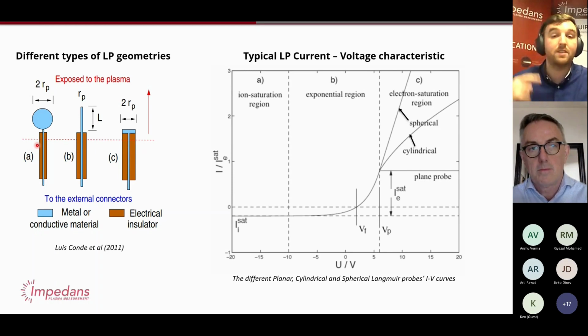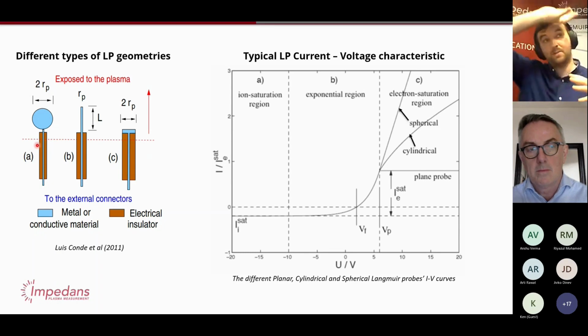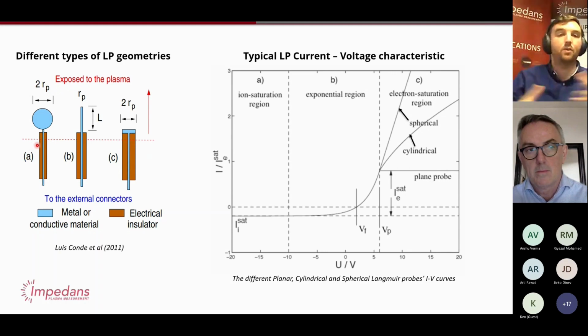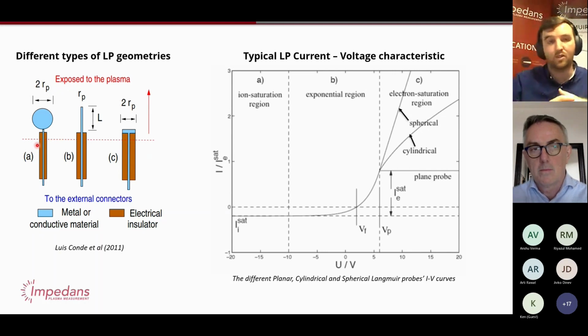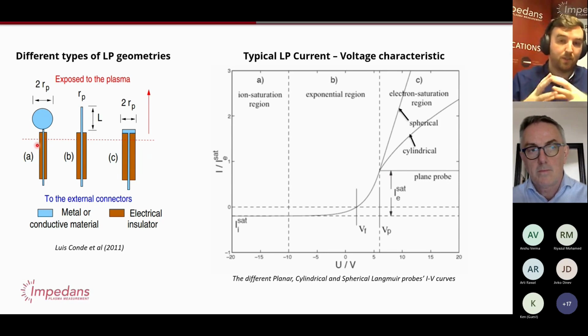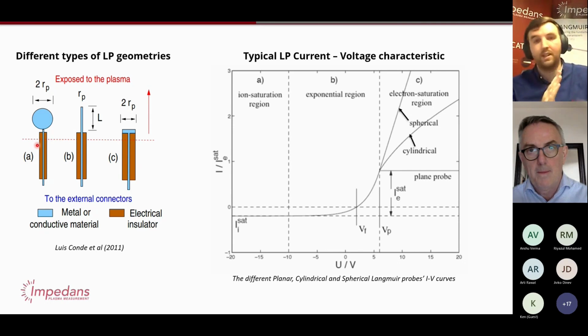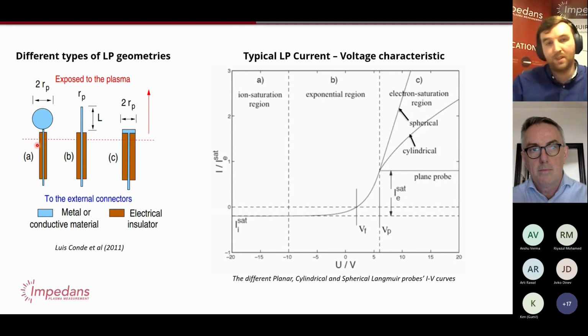Let's say also, if your plasma chamber is driven by a remote plasma, so you have a plasma that's separate and it's fed into the chamber and there's very low ion density, more of a reactive etch or something like that, to get any decent measurement you want to have a spherical tip. A planar tip is normally used when you want to measure something directional. So if you're looking at an ion beam tool, you might want to face the tip towards the beam, because you're not interested in anything that sputters off the bottom where the beam is colliding or off the walls. So planar is usually used for directional situations. But most people that we deal with stick to the thin cylindrical probe, usually most applicable for typical industrial plasmas.